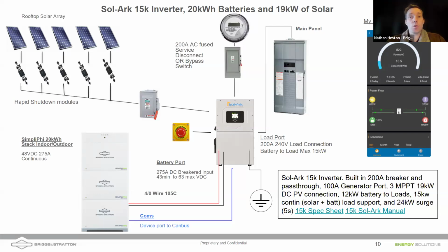I do want to mention that Sol-Ark has that PV disconnect built into the side. That's what that black switch on the left side of the inverter is. So as long as your inverter is installed outdoors, you wouldn't need that extra disconnect there. Sol-Ark's really thought of a lot in terms of, you could actually power the Keep Alive signal, the transmitter, for those AP Smarts right out of the Sol-Ark accessories bar, and you'll be showing that in a bit. Let's go to the next one.